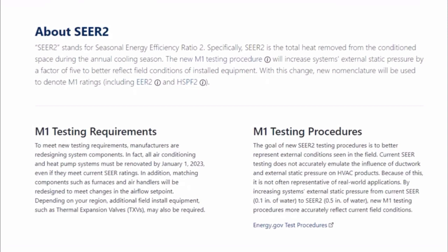Steve in the chat, which is HVAC Residential Basics, says he sees static pressure 0.7, 0.9, 1.2. He sees those weekly. So that's a significantly higher number, especially since that initial testing procedure, which was 0.1, which is just not happening. That's just not happening anywhere except for a very small amount of situations.